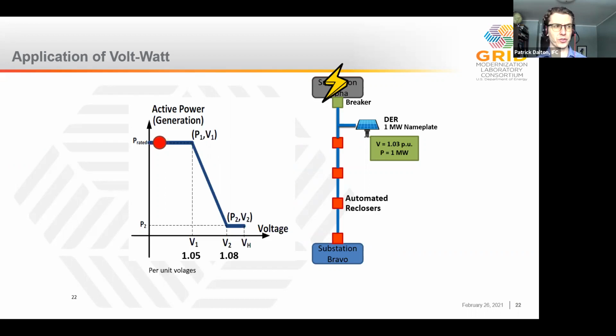What the volt watt function can do is back off the power to some level that is hopefully less of an impact on the system. It's sort of a soft shutdown, allowing the DER to still try to produce as much power as possible, but in a configuration it wasn't studied for. This function can automatically back off the power in a way that helps integrate it into the system and allows for system flexibility to switch this DER into different configurations without necessarily needing to do a detailed engineering study on all of those configurations.